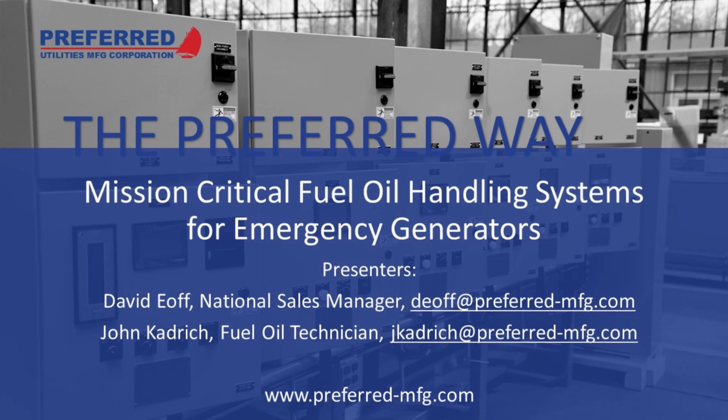One thing I did get some information from Alex Kenny, who chimed in. He did say, referring to that high level switch, that a return pump helps with that dry high level switch, since it can be tested completely by filling it above the return and then using the return pump to bring all that fuel back down. So basically you can test that if you have a return pump on your day tank.